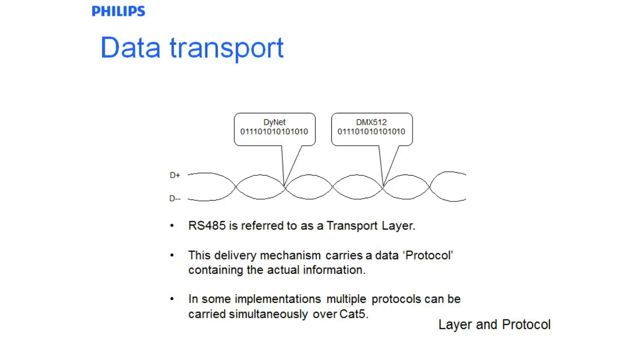In some implementations, multiple protocols can be simultaneously used over CAT5. In some instances, you can utilize DMX and Dynet on the same conductor pairs, while you could have a device that, once it starts receiving your DMX-512, it will obey it, but the rest of the time it is in Dynet mode. That is often done in performing arts centers.